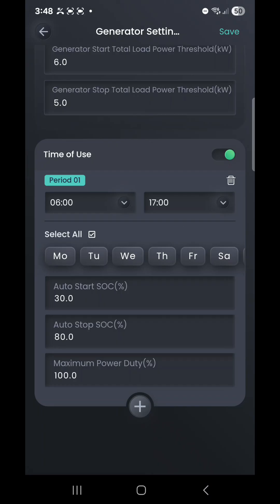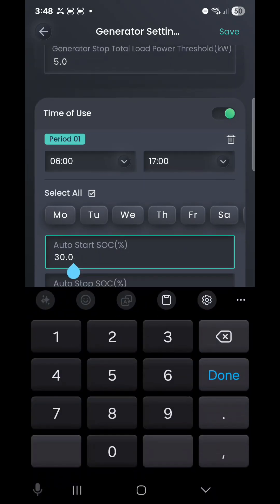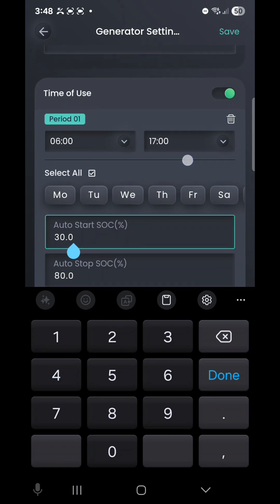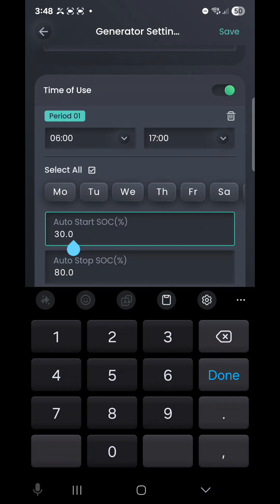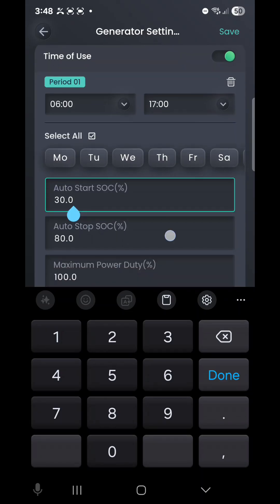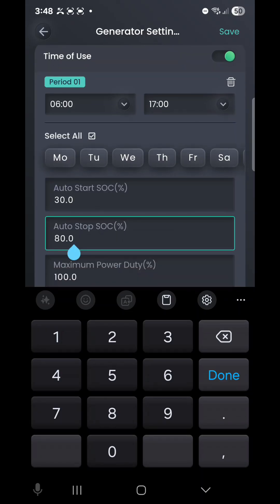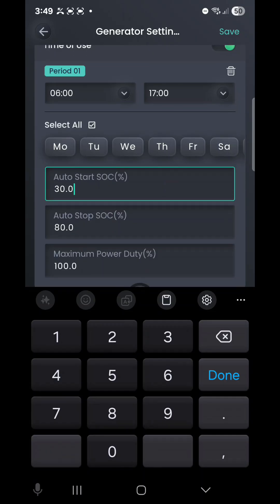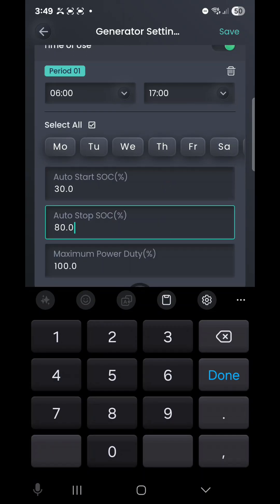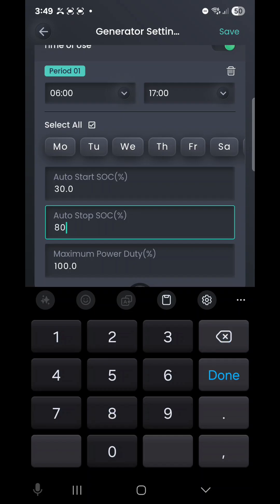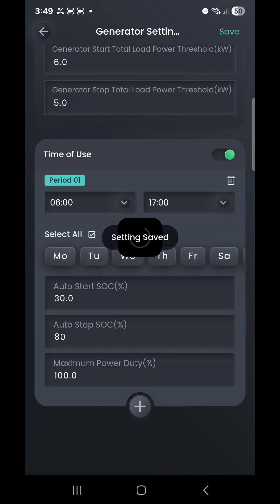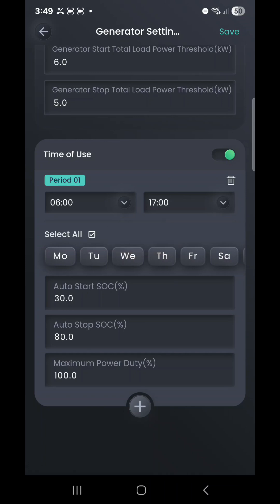Down here for the auto-start with this time-of-use rule, we currently have this particular customer site set up so if the battery capacity hits 30%, the generator will automatically fire up. That generator will then run until it gets to 80% at 100% power duty cycle. These are the two figures here that you can configure as the end user, so you can set to your requirements. We can up that to 100% if we like; 80% is generally the standard. Then we hit Done, press our Save up the top right-hand side—setting saved, there we go.